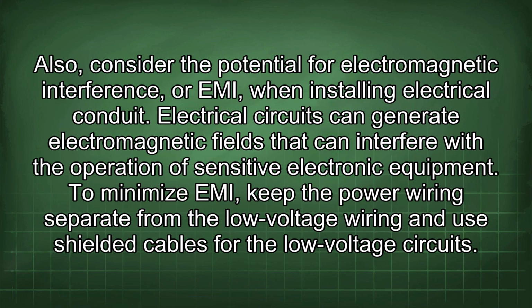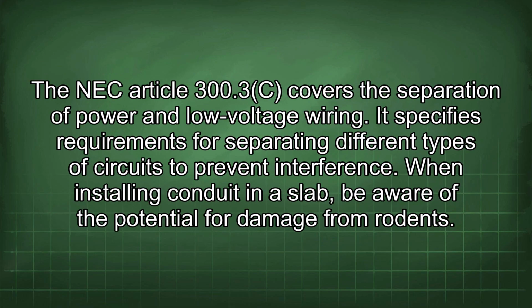Also, consider the potential for electromagnetic interference, or EMI, when installing electrical conduit. Electrical circuits can generate electromagnetic fields that can interfere with the operation of sensitive electronic equipment. To minimize EMI, keep the power wiring separate from the low voltage wiring and use shielded cables for the low voltage circuits. The NEC Article 300.3c covers the separation of power and low voltage wiring. It specifies requirements for separating different types of circuits to prevent interference.